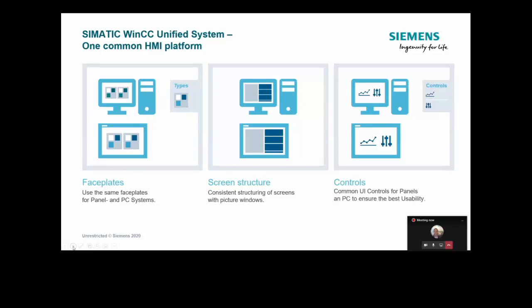This is a common HMI visualization platform across HMI and PC platforms. When going from a Unified Comfort Panel onto a PC-based platform, we're not changing the project — we're just changing the device and the project will scale and run on it. That means commonality of face plates — the face plates are exactly the same for the panel and the PC-based system. We use a common screen structure, for instance using a technological hierarchy. We have common user interface controls for both panel and PC to ensure the same usability across devices. The only thing to consider is the actual screen size itself.